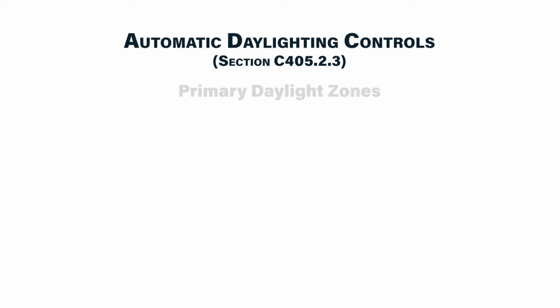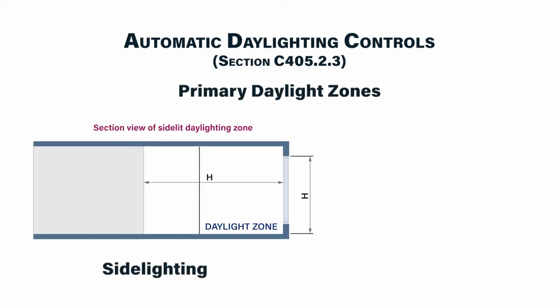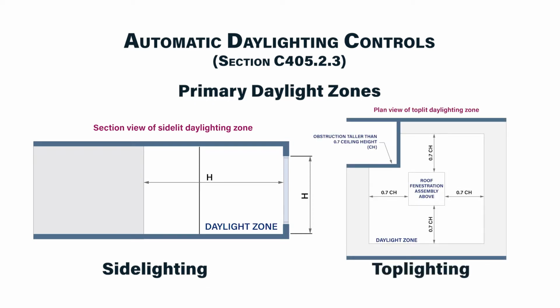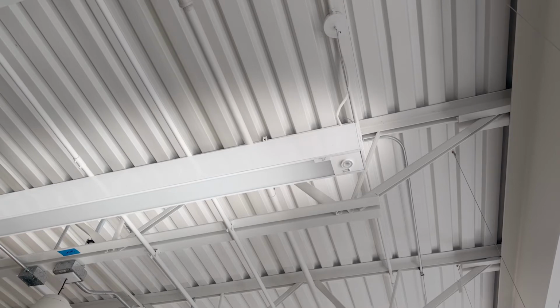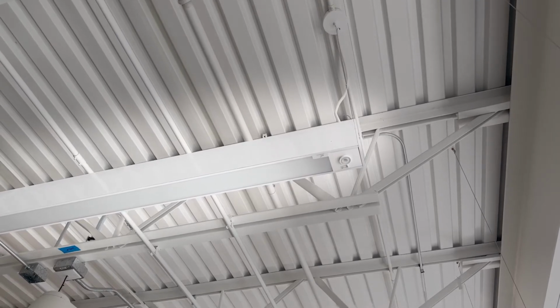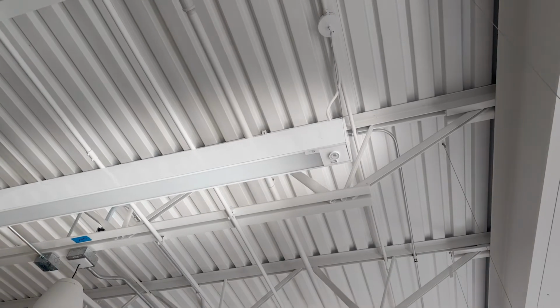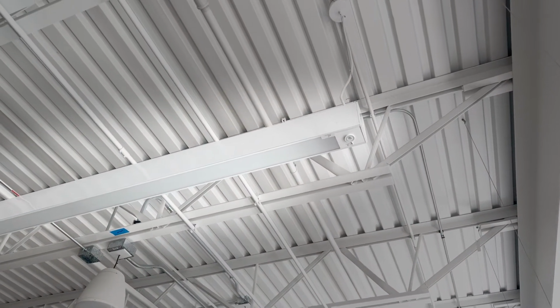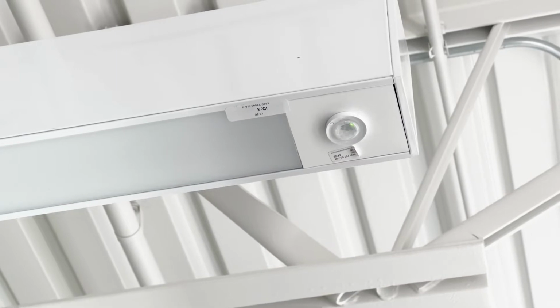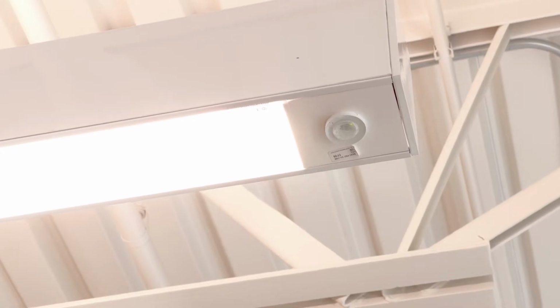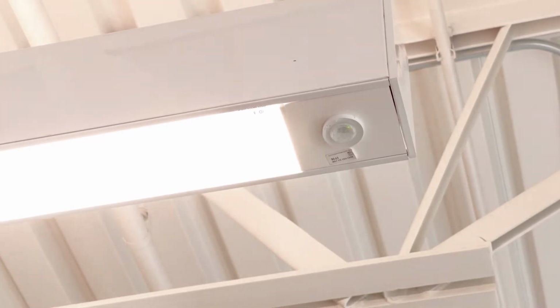IECC defines primary daylight zones for both side lighting and top lighting applications with diagrams to illustrate those definitions. ASHRAE further defines both primary and secondary daylight zones where these automatic daylighting controls are now required. Luminaire level lighting controls, or LED fixtures with integral daylighting and occupancy sensors, are a newer, market-ready technology.